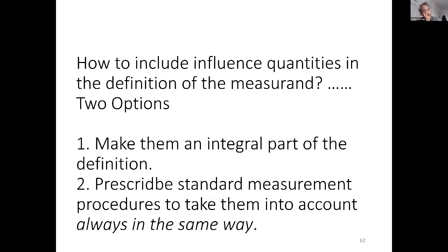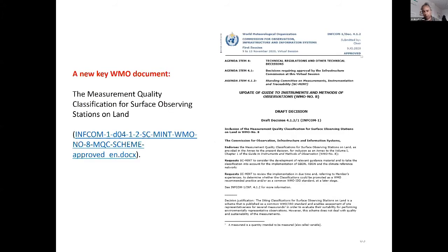You have two options. Either you make it part of the definition. For example, I only take the values of pressure when there is no wind, zero wind. I only take the values of temperature when there is at least 3 meters per second of wind, because I know that the radiation effect is then removed, it is not predominant. Put it into the definition of your measurand, and you're happy. Otherwise, you have to prescribe a procedure to evaluate it always in the same way. It's up to you to decide.